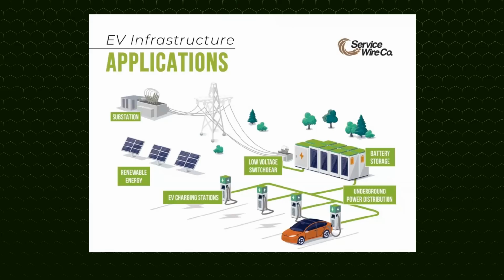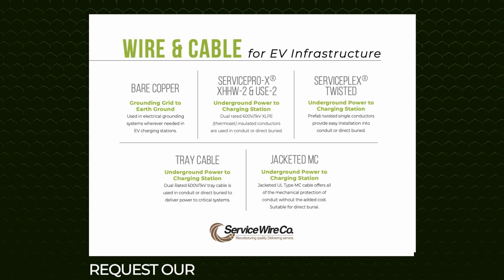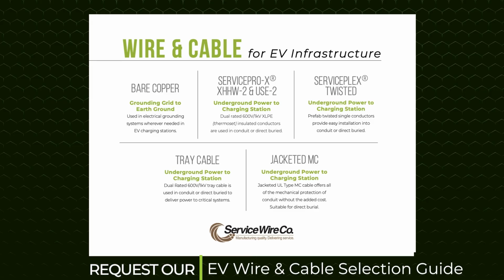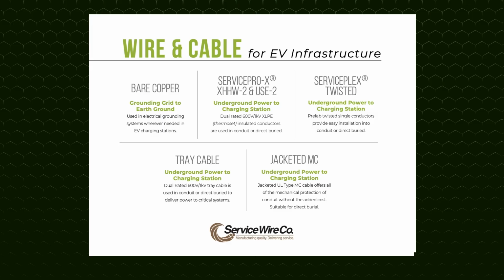It should be noted that ServiceWire's products are for static applications only. Our products are not suitable for the flexible charging cable that goes directly into the electric vehicle. As discussed, ServiceWire products can be used in an array of applications at an EV charging station. Our most widely used products are bare copper, Service Pro X single conductors, ServicePlex, tray cable, and jacketed type MC. Let's talk a little bit about why each of these products is preferred for this application.